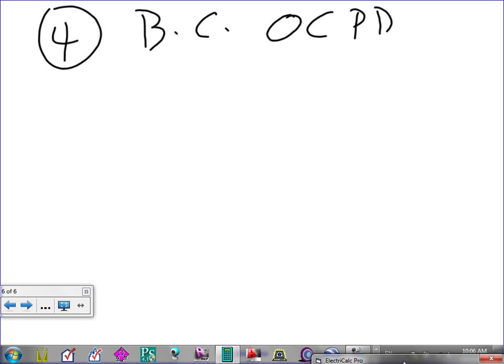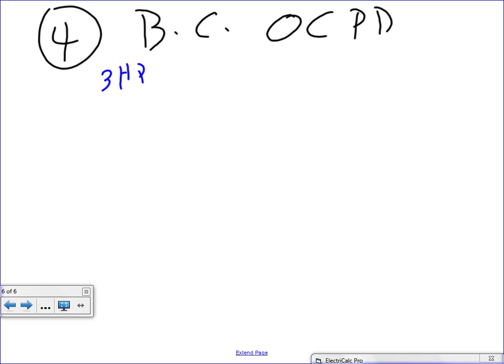Very cool. I want to give you guys the 3 horsepower. For 3 horsepower, you're going to go to the table directly. So let's do the math right on the spot. For the branch circuit, we're going to go to 430.52.